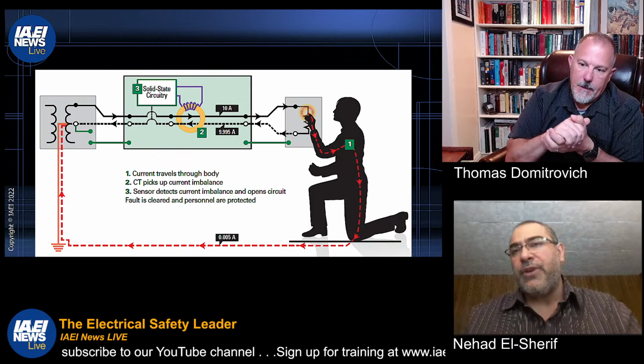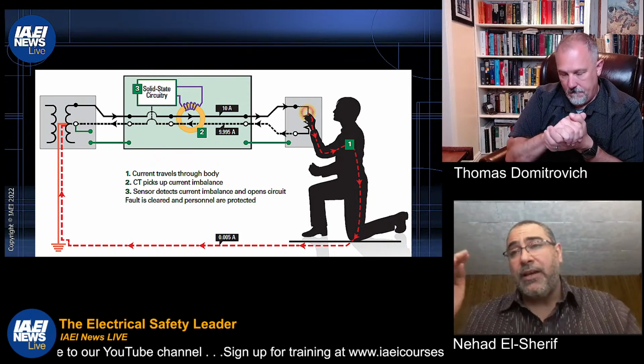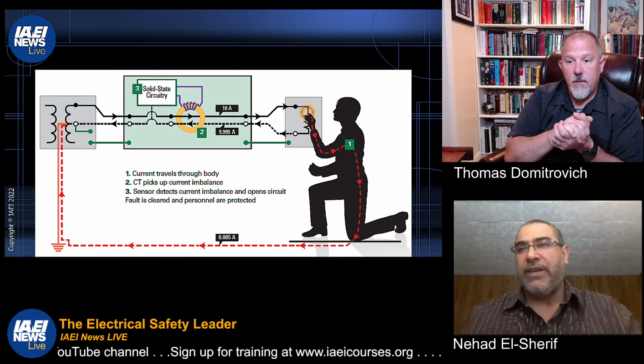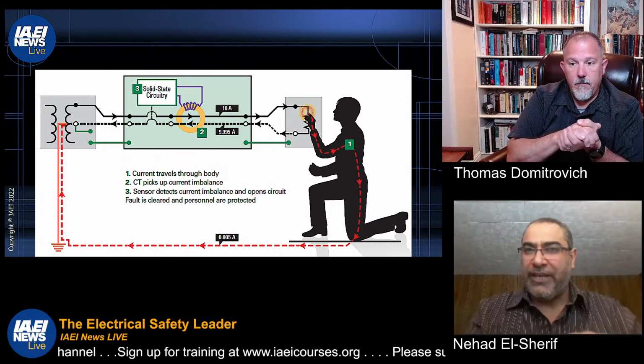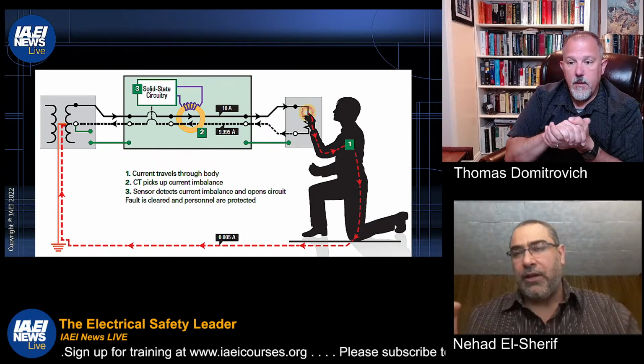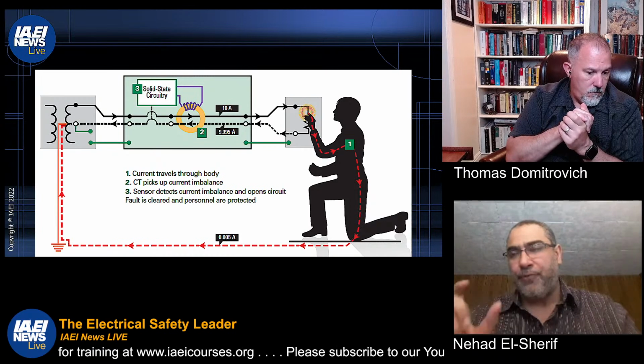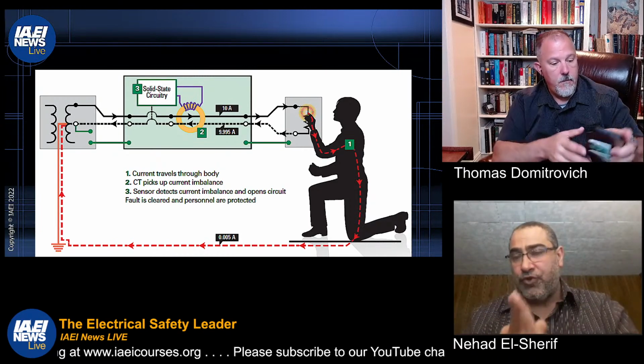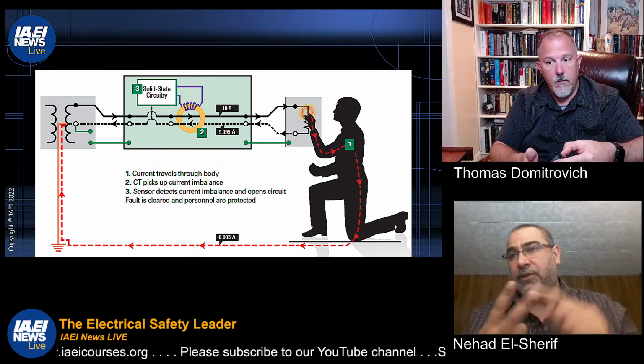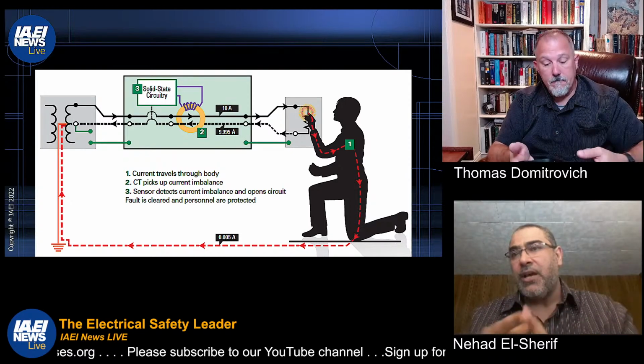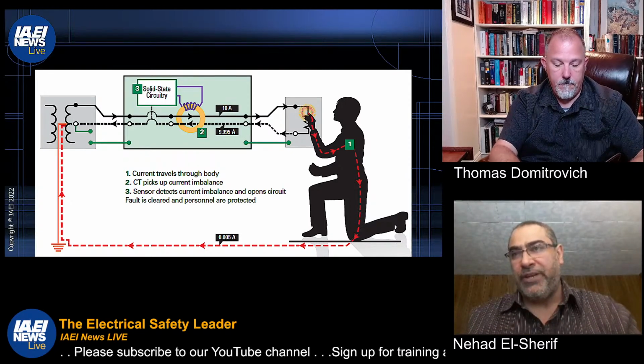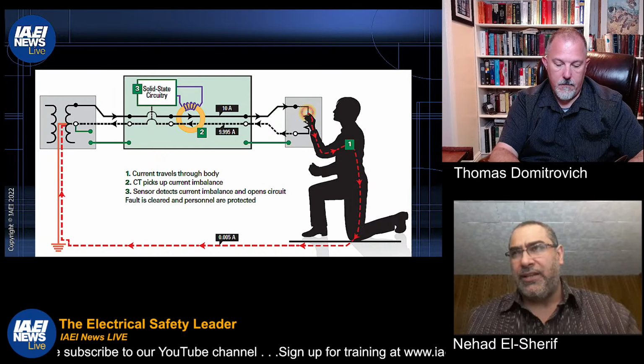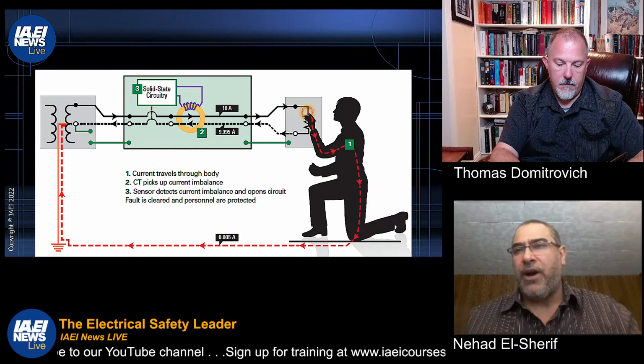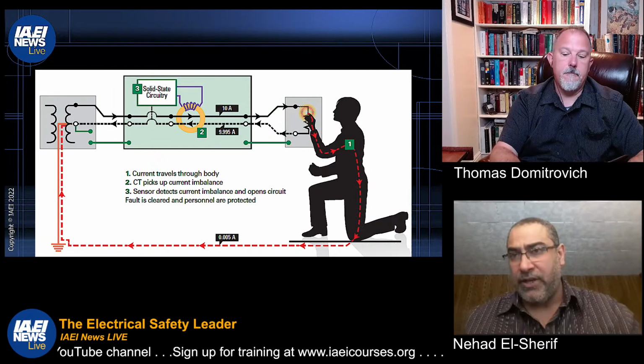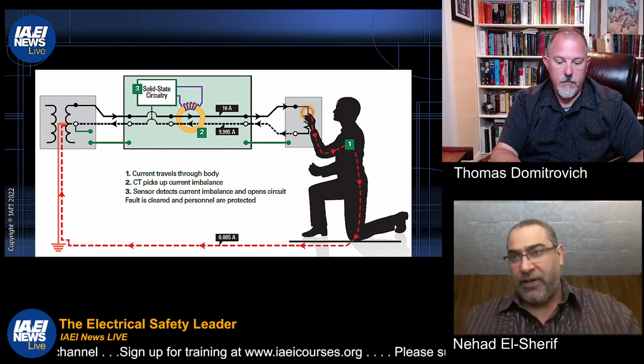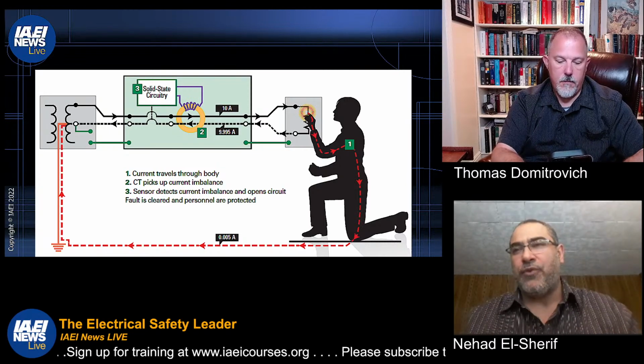Like you said, the 30 milliamps even allowed in marinas is still dangerous for humans. That's why we can use the 30 milliamps for personal protection. But the other thing I would urge people to think about when you think about personal protection is amps, for sure, milliamps, and time, because time is critical. Yes. For a machine, like Tom mentioned, 230.95 requires tripping within 1 second, right? And this is a lot of time for people. This will be enough to kill a person.